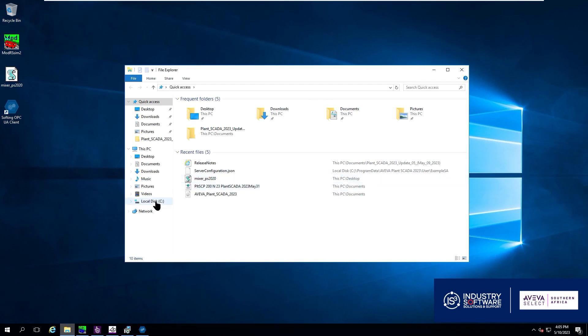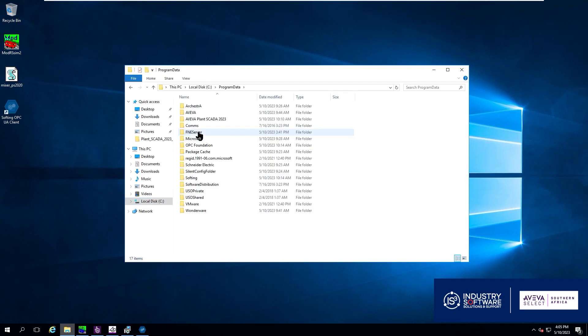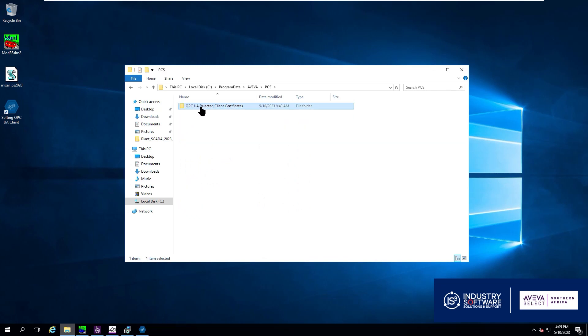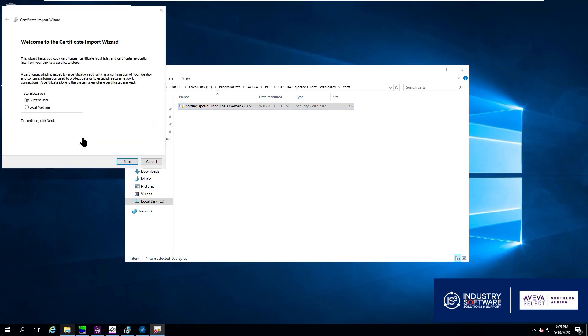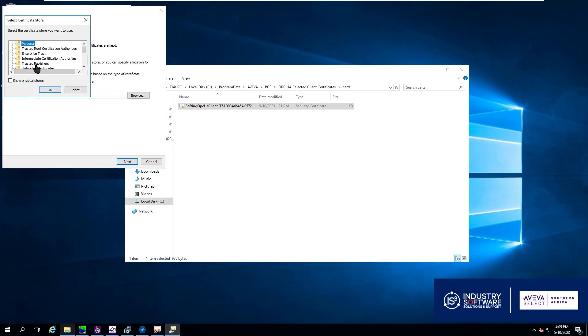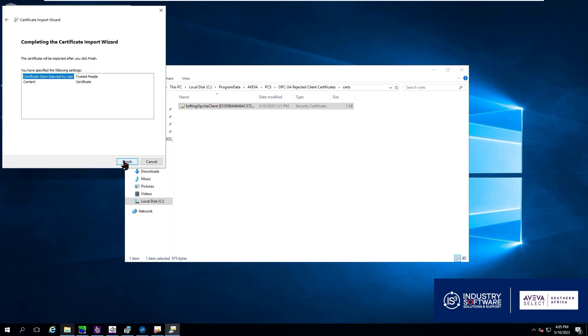So C drive, program data, we open up AVEVA and our PCS. In there we will see it's literally called a rejected certificate. We double click it and we want to install the certificate. We say you are allocating it to the local machine and we want to place it in a certificate store and that is going to be under trusted people. We click OK and we click Next and finish.